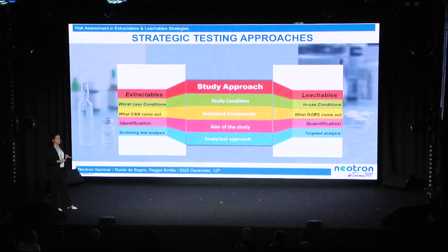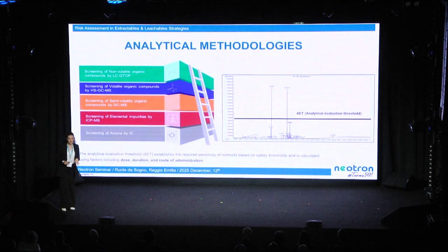And finally, the analytical approach, of course, reflects all these differences and all these needs. So for the extractable part, we have to work in a screening approach because, as I said, we don't know what we are searching for. So we are searching for everything. While for the leachable part, we have a targeted analysis because we know that these compounds are of concern. So we have to quantify it and to target it, of course. But in general, for the analytical methodologies, we need to work with orthogonal techniques.